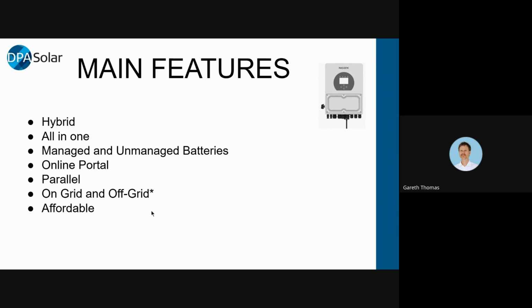I haven't got a bullet point about this, but it's a transformerless inverter, as opposed to your Selectronics or your Victrons, which have a nice big transformer in them. So they don't have the surge capabilities of those style inverters, which you pay a lot more for. Even though it does have a surge rating in the spec sheet, in practical terms it's really got nowhere near as much as a Selectronic or a Victron. That's because it doesn't have a great big transformer in it with henries stored in it, which gives you that surge capability. So you just have to factor that into your design.